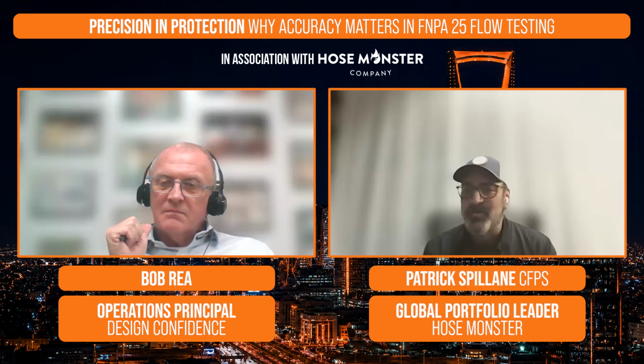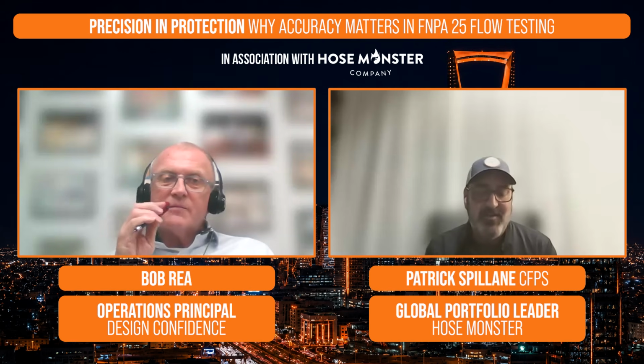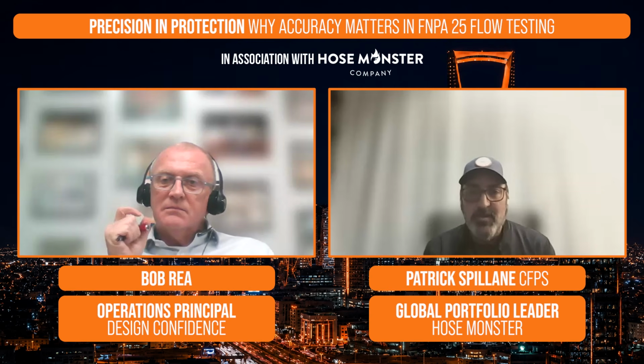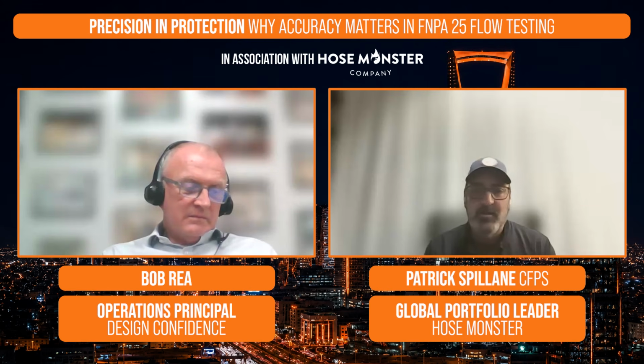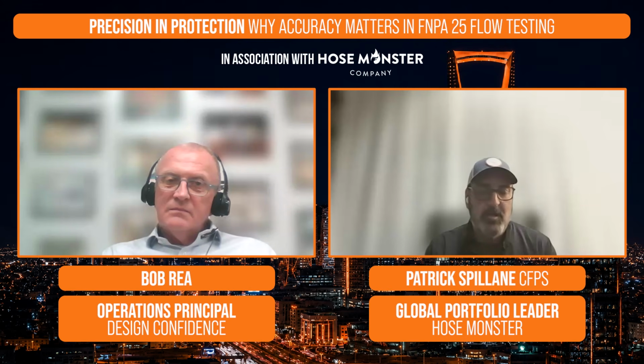So with that fire pump, we want to make sure we're turning it on, exercising it on a regular basis per code, which again could be weekly if it's a diesel engine, or some electrical engines as well need a weekly churn as well too. There's certain setups that require that. So there is quite a few details, right, that we can kind of keep going into of what to be looking for on those tests.